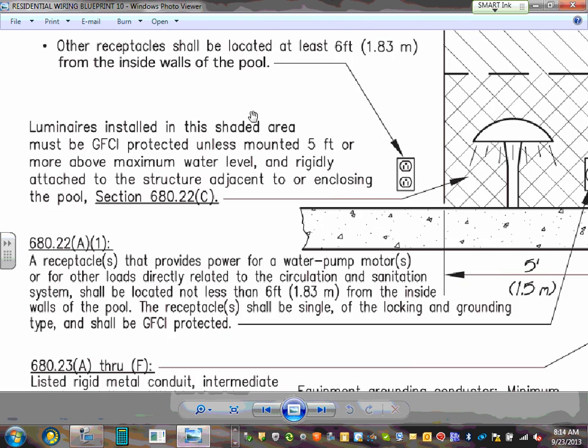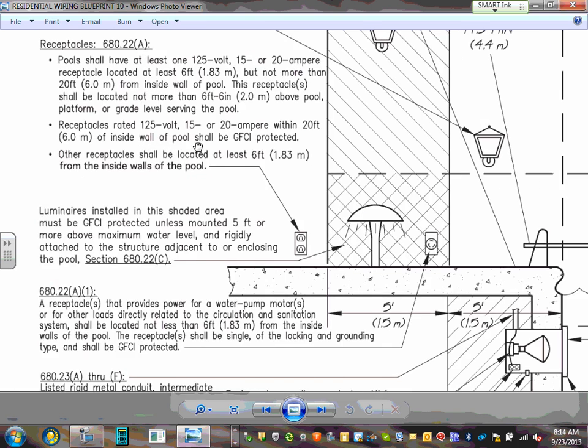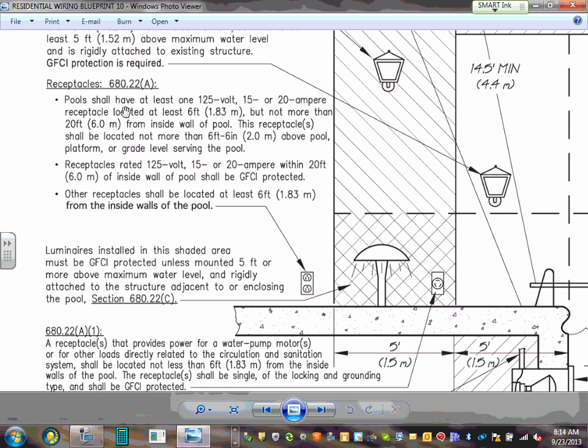I want to bring to your attention, guys, here you require a receptacle. The NEC code book requires a receptacle not closer than 6 feet, not further than 20 feet away, a GFCI receptacle. You have to have at least one receptacle. Not closer than 6 feet, not further than 20 feet, GFCI.